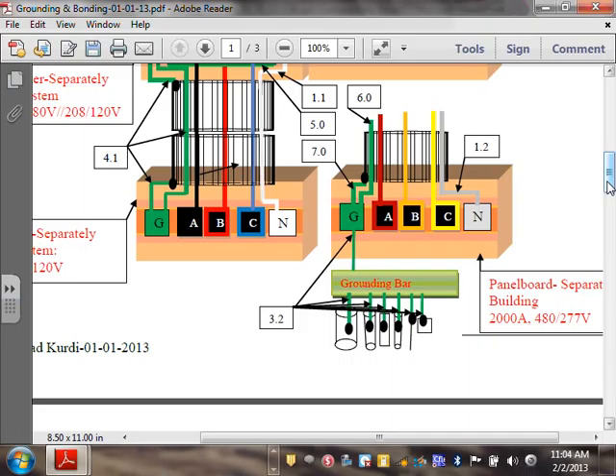Now, number 6, guys, there will be a conductor in every set of conduits, right? Because at 2,000 amp, you typically divide them. So we have 2,000 amp, divide by 5 will give you 400, right? You can pull 600 runs here. So how many? 4 sets of 600, or 5 sets of 600. Okay, so then for these 5 sets, you need to pull 1 conductor in every set.